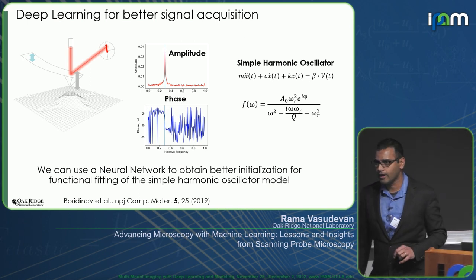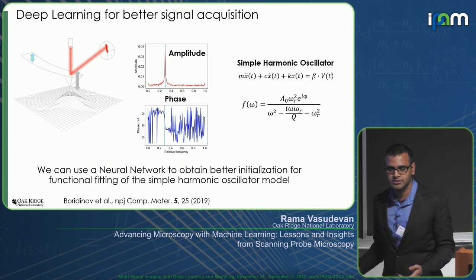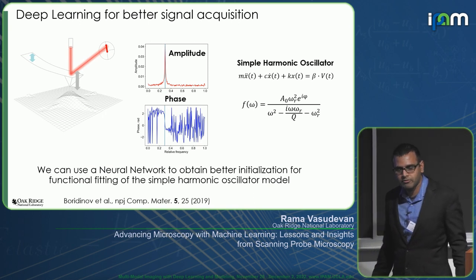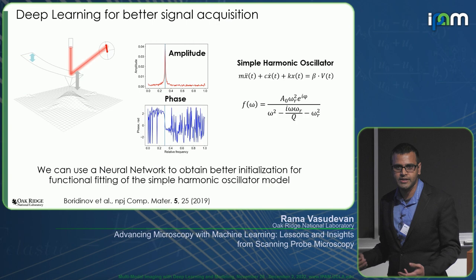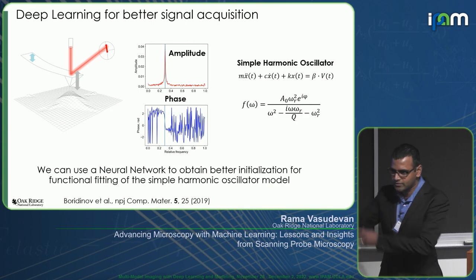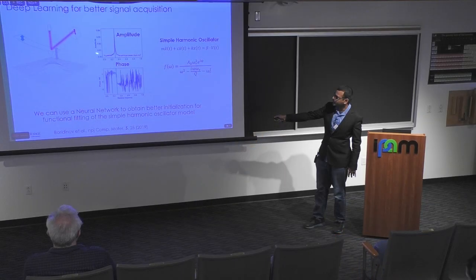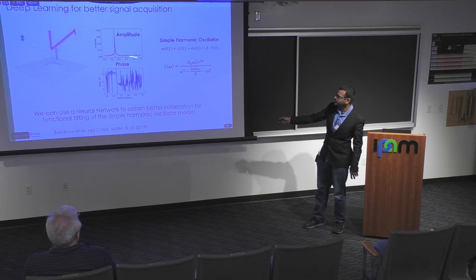As I mentioned, in order to interpret signals coming from the AFM, very often if we're working in some resonant mode, we need to understand the cantilever dynamics. You have this cantilever resonating on the sample surface, and typically we have to choose a model—it might be a simple harmonic oscillator model. This is a linear system, and it's very easy to solve.